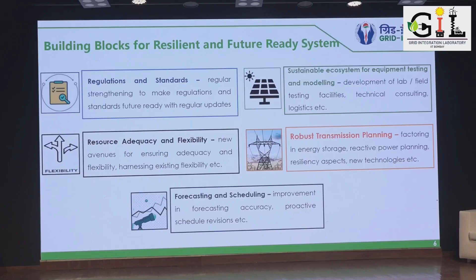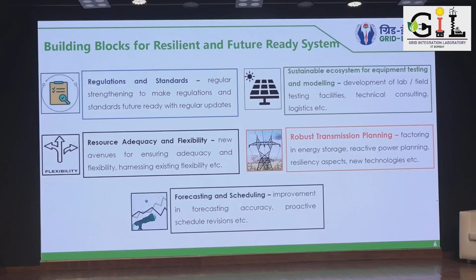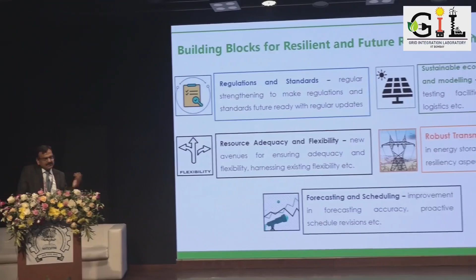As per CEA regulations, they can go up to 3% per minute, but most plants are currently operating at 1%. We need to go higher from this convention, because our largest fleet is thermal power plants. But other resources, whether hydro or gas, whenever they are running, also need to contribute, because they can ramp up faster. So that area is important.